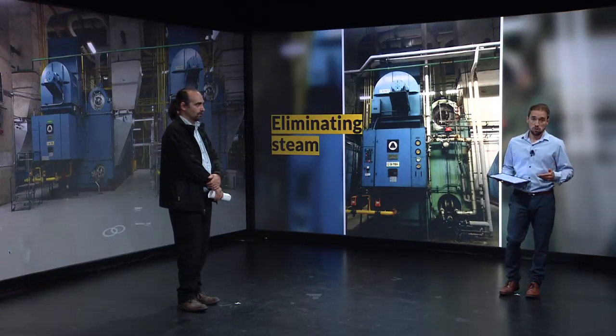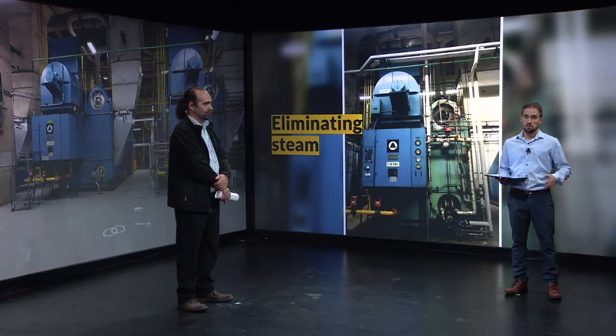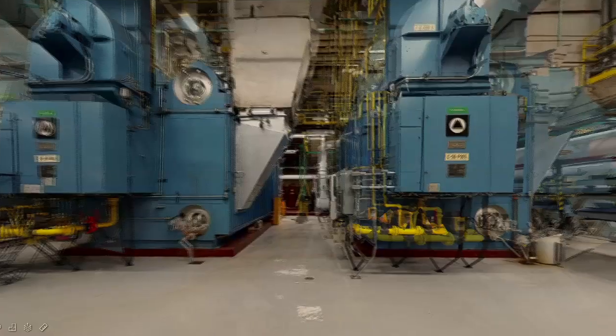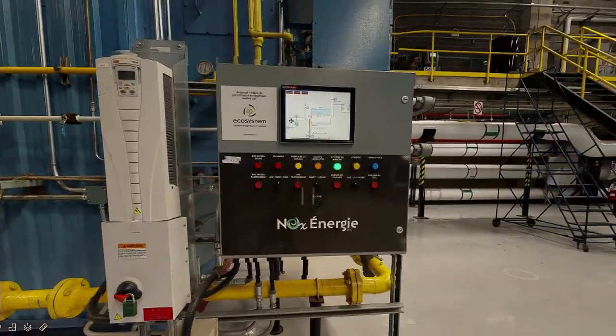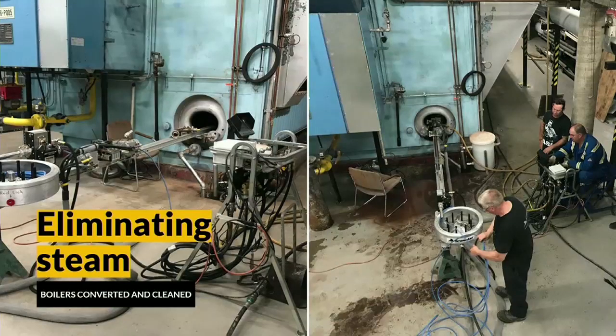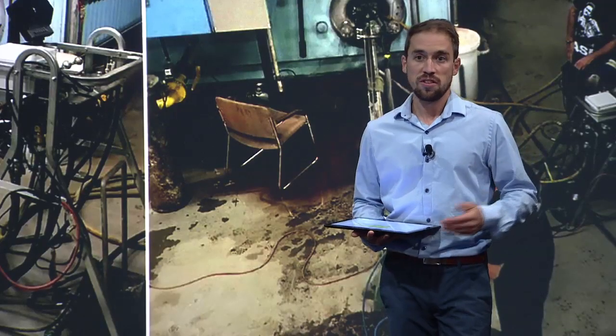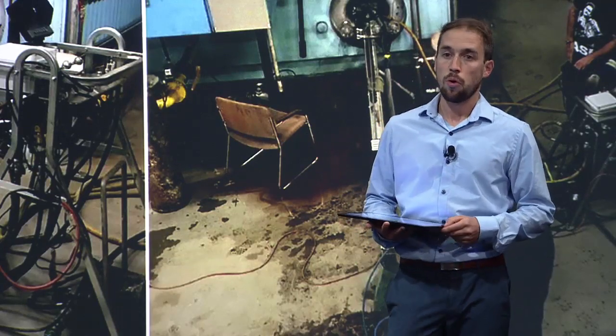We also updated the controls on it, installing new controls with VFDs. We converted the pressurized vessel, making modifications to make sure it could produce water instead of steam without any failure. We added a flue gas heat recovery to increase efficiency as well, and we reduced the capacity of the burner by around 20%, as part of the global strategy of reducing operational cost. That also helped reduce the surveillance requirement for the stationary engineer in the boiler plant.